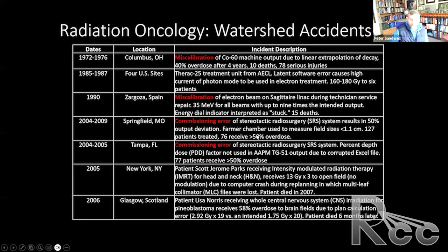So you got to think that's probably led to a lot of radionecrosis and increased toxicity. Another commissioning error in Tampa. This was due to the wrong PDD factor used. Again, significant overdoses. And I'm highlighting the fact, miscalibrations, commissioning errors. Again, this goes back to a physician's mistake is personal. A physicist's is universal. These things are not good. Then these other ones in 2005, 2006, these were some events that were highlighted. There was a series of articles in 2011 in the New York Times that highlighted some of the dangers in radiation therapy. And this one's due to MLC files, and the other one is due to a plan calculation error. These are some serious things that can be caught, hopefully caught before they cause too much damage.